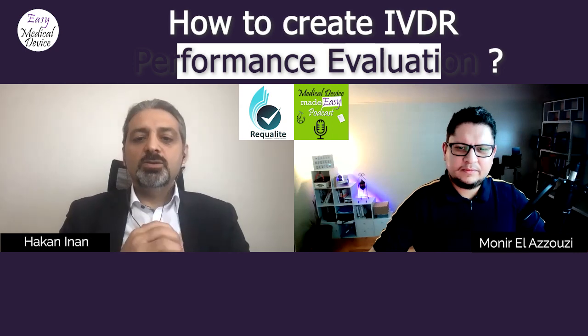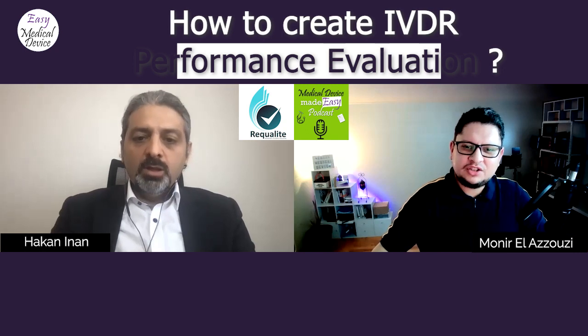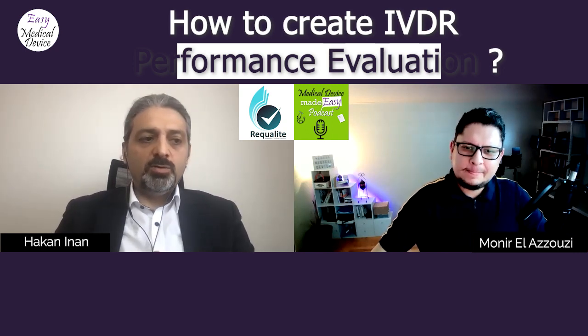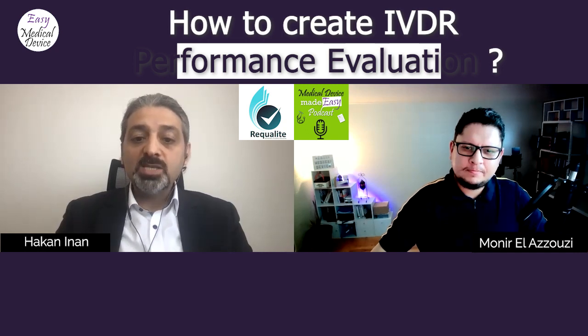So, are you getting many patients? Like, you have to define a certain amount of samples to prove that your clinical performance is correct, the same as when we are doing a clinical investigation? That depends, Munir. It depends a little bit, of course, on the classification of your device. As the risk of the device increases, so does the amount of data, remember that clinical evidence I mentioned, sufficient amount of good quality data. As your risk class increases, the amount of data you need to provide also increases. So you need to provide more data.